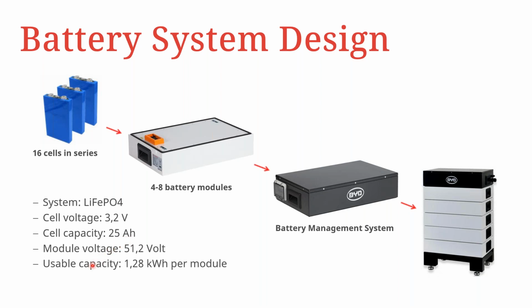To obtain the usable capacity, you multiply the cell capacity, 25 ampere hours, by the module voltage, 51.2 volts, giving a total of 1.28 kilowatt hours per module.